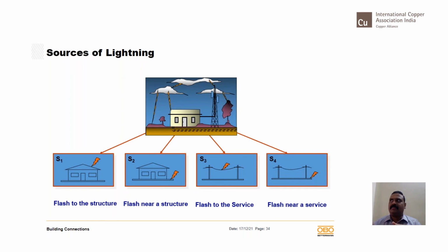The fourth possibility is a lightning flash near a service. It does not necessarily have to hit this building. Probably it can hit in an area where you have a substation outside the building area, or even just far away. So all four possibilities are to be considered when you design foolproof lightning protection for the building. Unless you take into account all four sources, the protection measure cannot be sufficient.